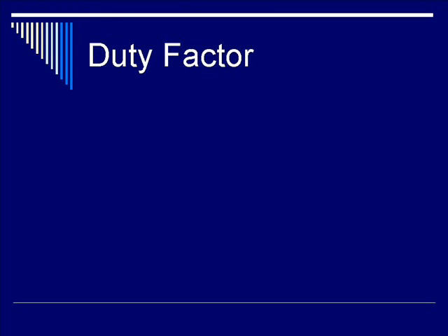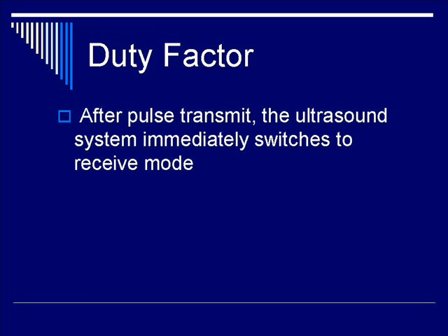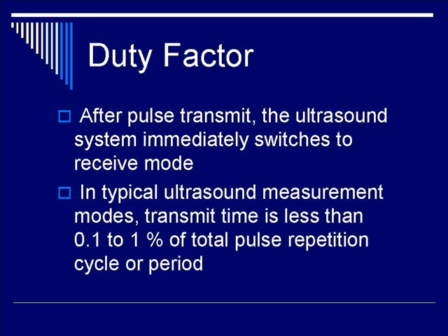We will now talk about pulsing characteristics. In particular, let's discuss duty factor. After a pulse is transmitted from the transducer, the ultrasound system immediately switches to receiving mode. For a typical ultrasound system, the transmit time is generally less than 0.1 to 1% of the total pulse repetition cycle or period.